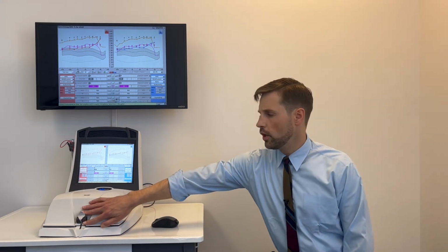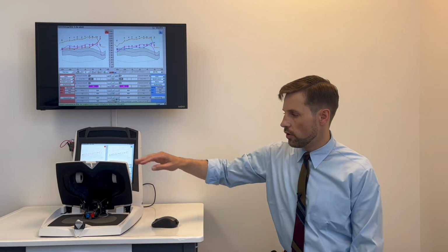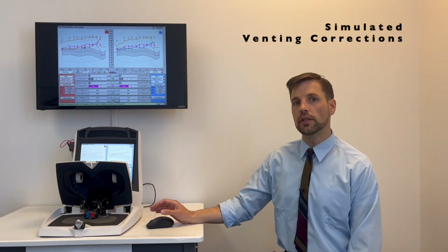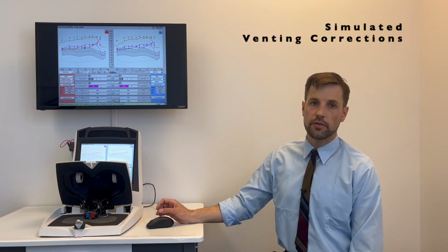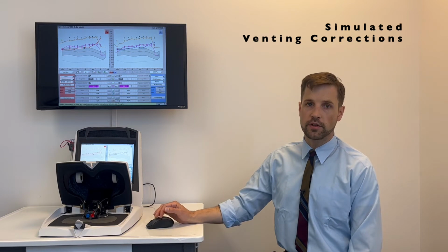Verifit2 is very much a fully featured real ear system. In fact, you can't buy it without the test box, so we can't do a review of it without talking about the test box. It is one of the only binaural test boxes. You can plunk in the venting that you have on the ear mold or the hearing aid, and you're going to get a much better approximation of the actual venting that you would have in the ear.